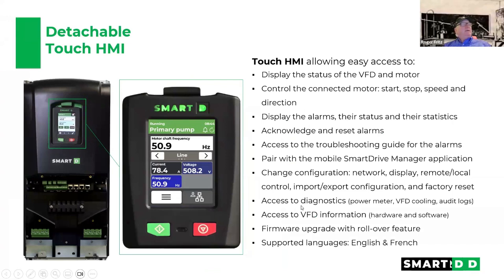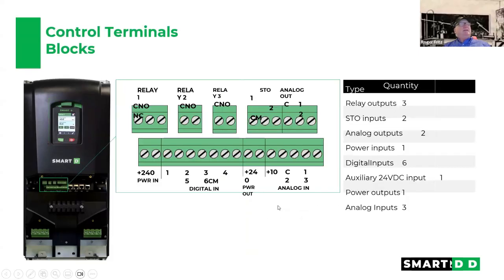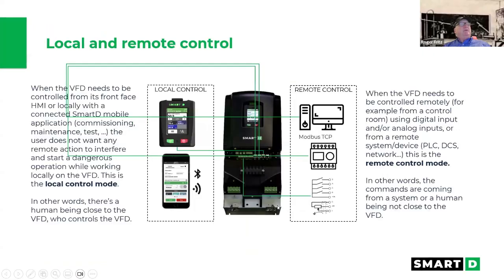A little bit about the front end of it. It's a touchscreen based front end. So as updates or changes happen, you're able to download that in very easily. And this is the configuration of the I/O that are in there. It's got the Modbus TCP here, and it's very user-friendly through networks. So you can, from your iPhone, there's an app that you can basically program the drive. If you have set up programs, you can download them and dump them very quickly into the system.